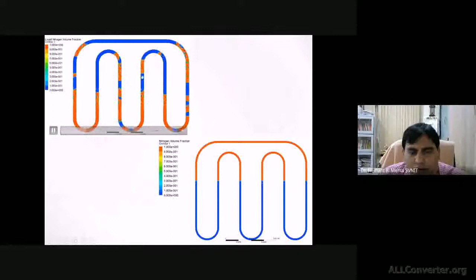But what is the effect of diameter during this phenomenon? That is very interesting. You could see here that this goes up. Now, if you see, it is not trying to move up much. But if you observe the phenomenon in this case, see, this is slipping of these droplets. So this slipping means gravity prevails. You could see here, this is slipping here also. Slipping means gravity attracts the liquid downward. And since it is falling, we do not have the falling mechanism in the condenser. If it is a falling case, this is not going to transfer the heat effectively. So it was our first simulation with the larger diameter where we did not get the proper pulsation, circulation and effective heat transfer between the evaporator and the condenser.